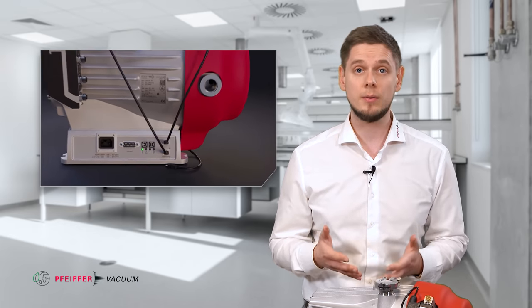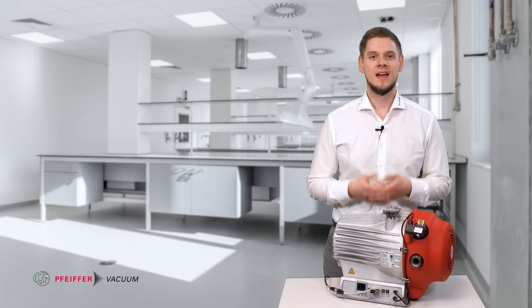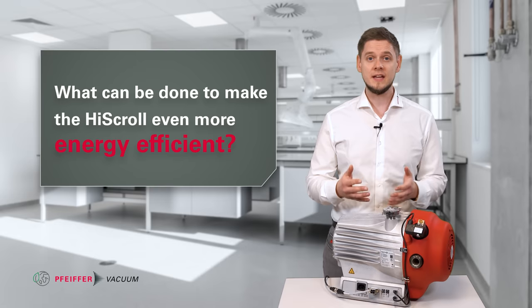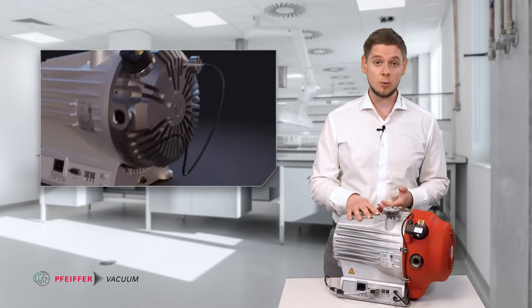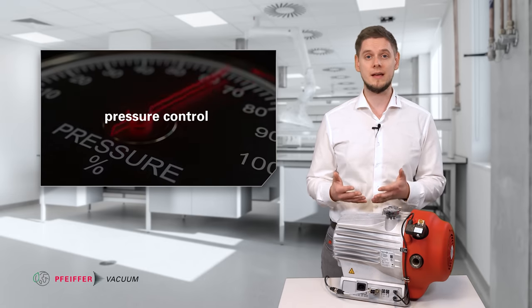You can save even more by using the intelligent operation modes with the new accessories of the HiScroll. Our intelligent HiScroll can control your target pressure fully automatically. Thanks to the integration of the optional RPT 010 pressure sensor, the HiScroll is constantly aware of your vacuum pressure in the chamber and automatically regulates its speed to maintain the target pressure. So the HiScroll can run at reduced power to achieve the same result, for example backing turbopumps — guaranteeing energy savings because only the vacuum that is exactly required will be generated.